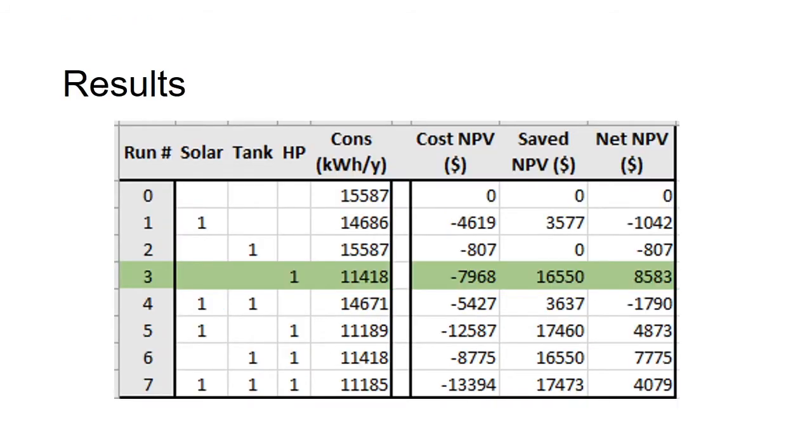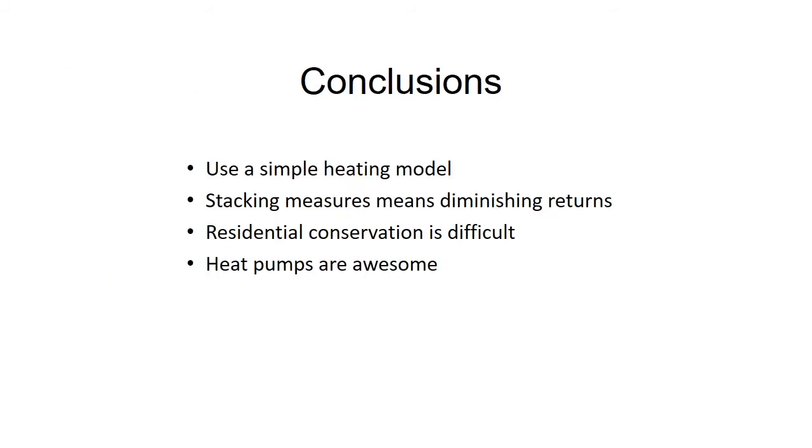I was frankly a bit surprised to find that I can actually save money by installing a heat pump. Wrapping up, the main things to learn here are: 1. A simple heat load model will work well enough. 2. Pick the low-hanging fruit and ignore the rest. 3. If you're not spending much money, it's hard to save money. And 4. I should get a quote on a heat pump.